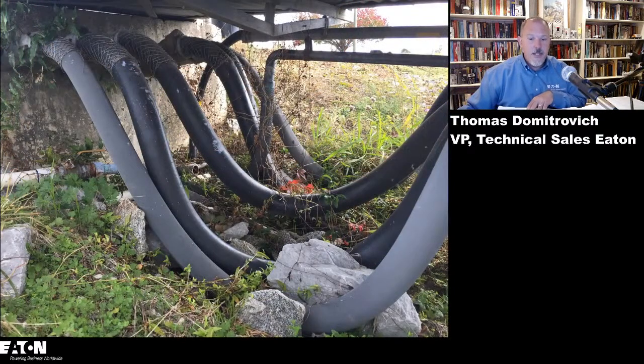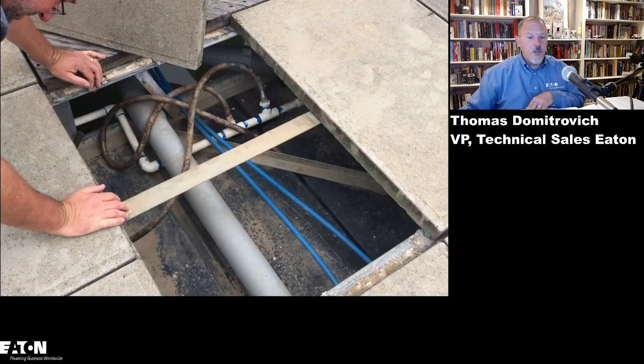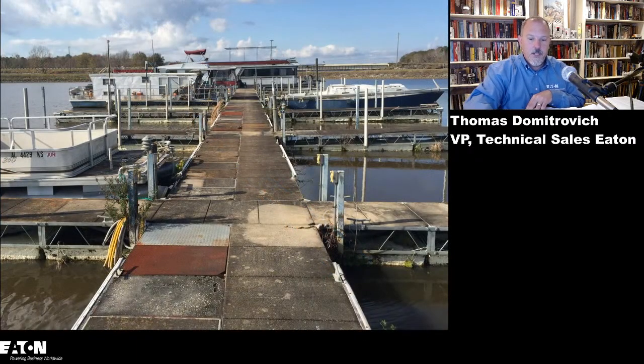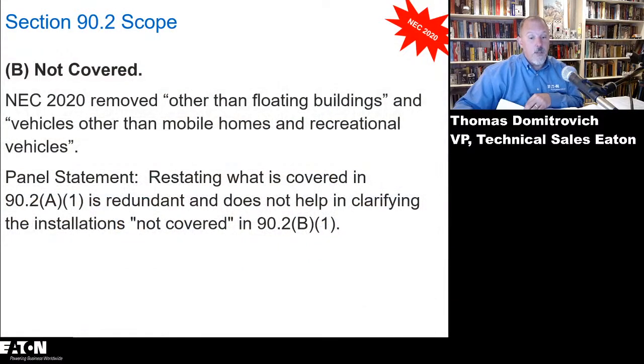But either way, we made some changes to accommodate that. We have multiple feeders going out to these locations. You'll see conduit and raceway out there, and that panel that we picked up - these are cement pads, and you can pick any one of those up and see all of the wiring underneath. You'll notice these are providing shore power that, if installed today, would not meet the National Electrical Code requirements.